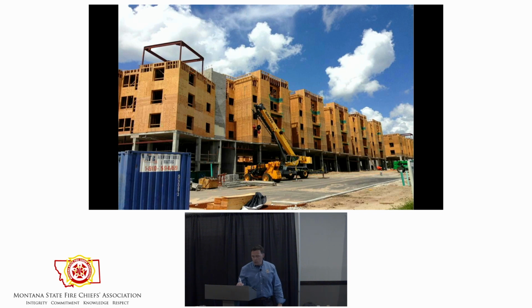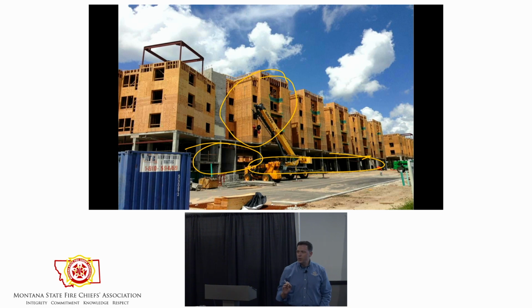And I agree with you, but the reason I use this one, NFPA 13 in a commercial setting is going to say, hey, look, you got to sprinkler everything unless it's non-combustible. So that story of the Heckman fire, there would have been sprinklers per NFPA 13 in a combustible space if it was sprinklered per NFPA 13. Now here's that mix of prevention into our operations. In this case, we would put sprinklers everywhere in this part of the building per NFPA 13. It could be a parking deck. It can be mercantile. It can be whatever. But in this, because we're calling it a separate building, the combustible spaces, that sprinkler protection system is put in per NFPA 13R. So we have 13 is everywhere. 13R stands for residential, up to 4 stories in height. Now, because those are separate buildings in this weird code anomaly, that's considered a 4-story building.